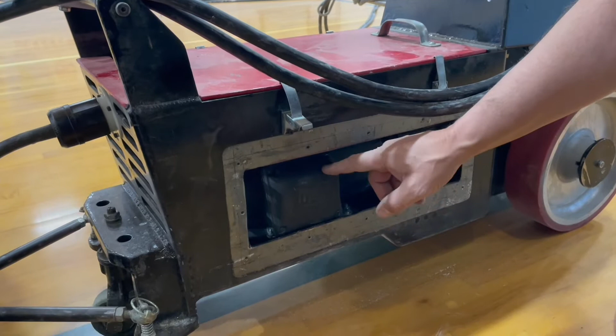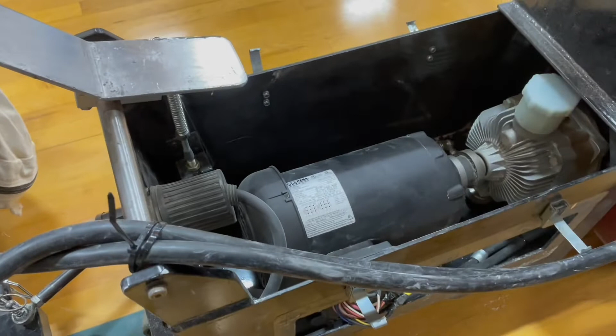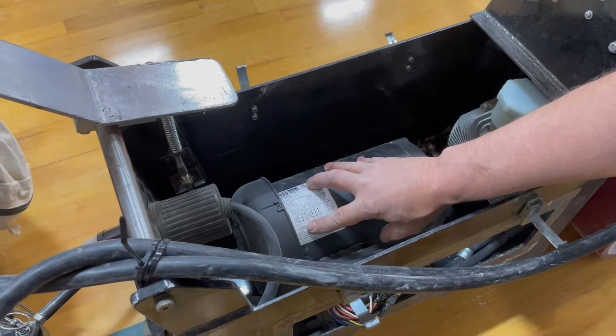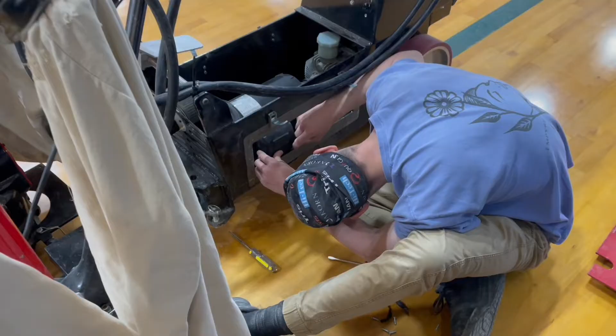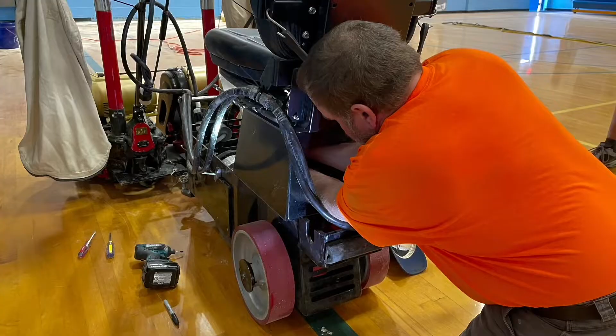Let's bring the camera in here. We've taken off this access panel, taken off the electrical cover off the motor, and I had to take the top access panel off too. Now I get at the actual plate here, and even though this is a different motor, you can still see that line 1 goes with 1 and 7, hot line 2 with 2 and 8 - that's low voltage. In other words, it's exactly the same, even with a different motor.